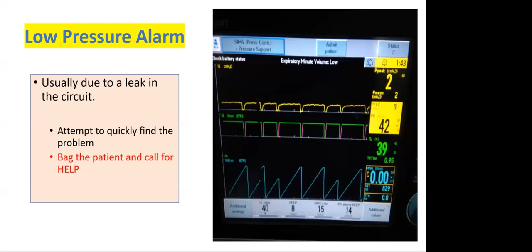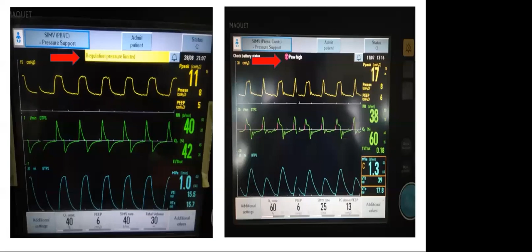So low pressure alarm, again like a low volume alarm, you have to see for any leak, you have to see for the cuff and reinflate if needed. You can see here, what is it showing? Regulation pressure limited. Okay, and here also pressure is high. So what does it mean? It's a high pressure alarm.